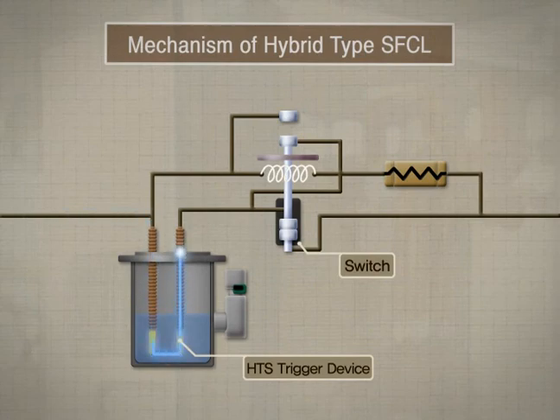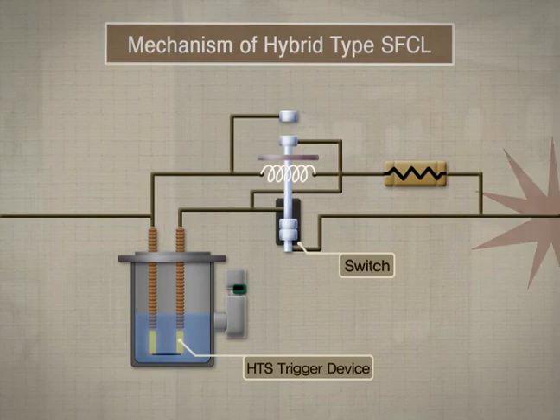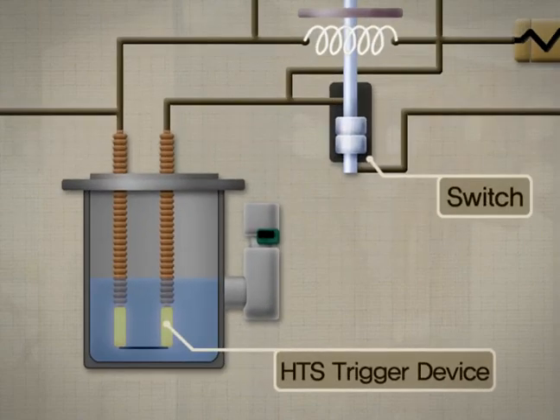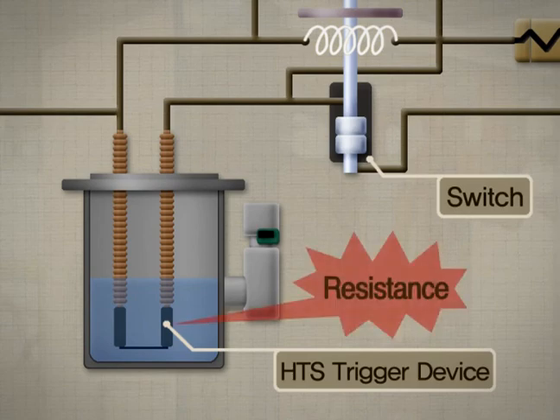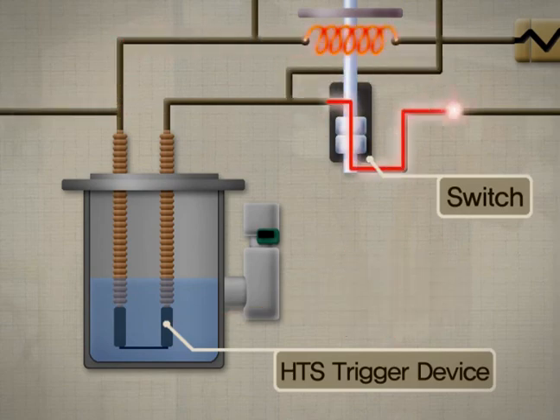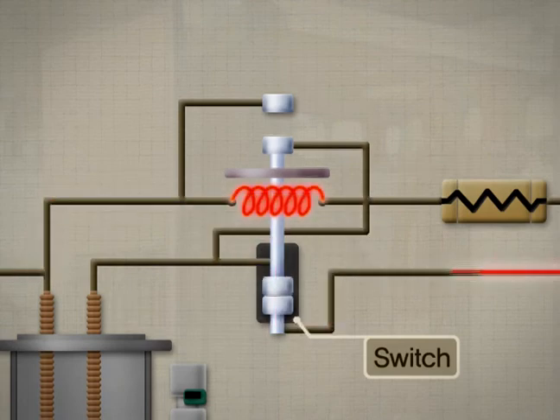Under normal conditions, the power flows through the main path of the HTS module and the high-speed switch. When there is a fault in the power grid, a fault current passes through the HTS module. The fault current is far greater than the critical current of the superconductor. Therefore, the HTS module loses its zero resistance property and becomes resistive. The transition triggers the switch to cut off the main path.